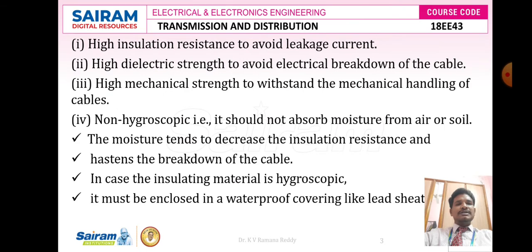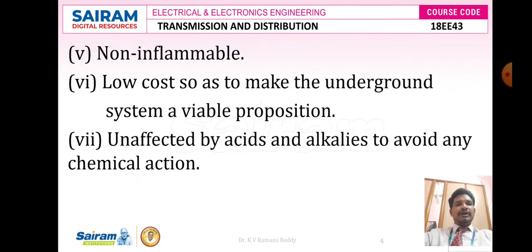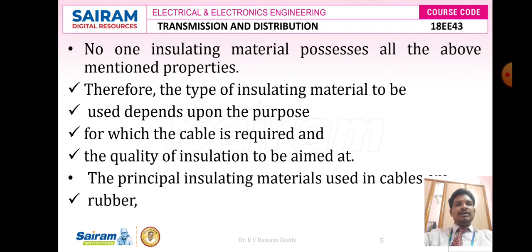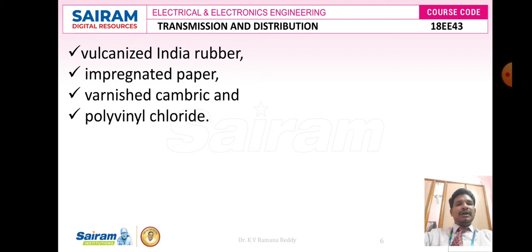The material should possess high physical stability, chemical stability, be non-inflammable, and be low cost. Then only can we prefer underground cables and their insulating materials. No single insulating material possesses all the above-mentioned properties, so the type of insulating material used depends upon the purpose — the type of service and the amount of voltage. The principal insulating materials used in cables are rubber, vulcanized India rubber, impregnated paper, varnish cambric, and polyvinyl chloride.